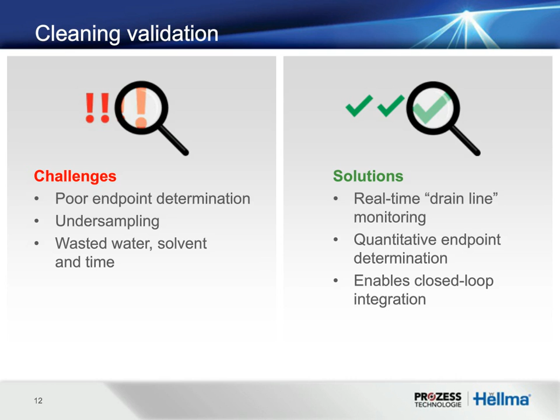This is a quick diagram of how this cleaning validation actually works. So if this is our apparatus here, the gray box installed on one of the drain lines, we can send the analyzer control, wired or wirelessly, depending on where the unit is, to control the spectroscopic aspects of it: how quickly it's making a measurement, integration times, the wavelength ranges that are going to be used, and so forth. And from that, a spectrum is acquired, and in a lot of cases, the spectrum is not the endpoint. They're converting that spectrum into the constituent monitor, which is typically the most dangerous compound in a formulation, or all compounds in a formulation.